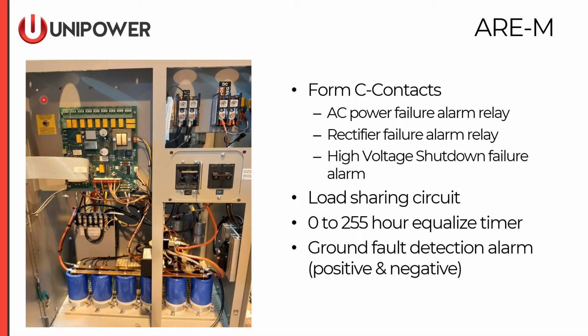Load sharing is a standard feature on all these ARE-M chargers. It only requires a single 18-gauge wire terminated between the load share terminals of each charger to be included in the load share scheme. We can load share, the typical application is just 2 chargers, but we can extend that to 3 or 4 or even 5 as necessary.